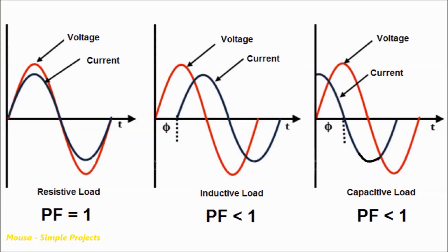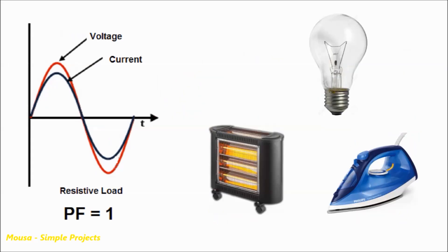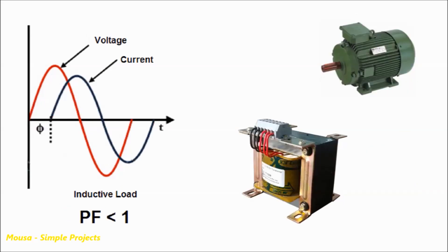The power factor is a number from 0 to 1, which refers to the phase shift between voltage phase and current phase in AC appliances. The power factor in resistive loads such as incandescent lamps and heaters is equal to 1 — that means there is no phase shift between the voltage phase and current phase. But the power factor in inductive loads such as motors and transformers is less than 1 because the voltage and current are out of phase.